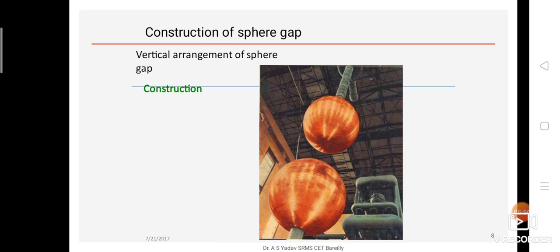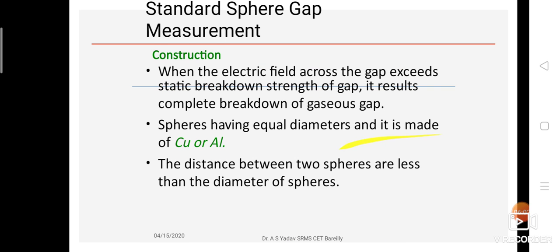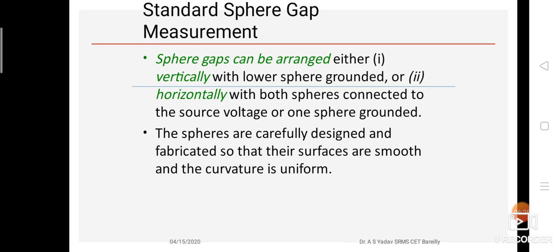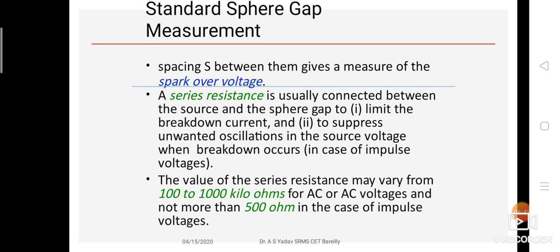This is the actual lab diagram, a lab figure of the kind found in laboratories where we can measure the value of high voltages. The construction: when the electric field across the gap exceeds the static breakdown strength of the gap, it results in the complete breakdown of the gaseous gap. The spheres have equal diameters and are made of copper or aluminum. The distance between the two spheres is less than the diameter of the spheres. The sphere gap can be arranged either vertically or horizontally. The spheres are carefully designed and fabricated so that their surfaces are smooth and the curvature is uniform. Spacing S between them gives the measure of the spark over voltage.